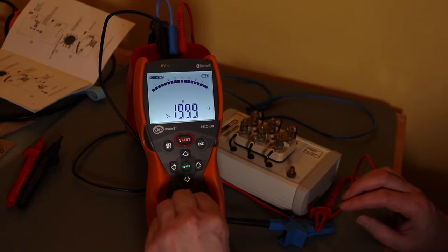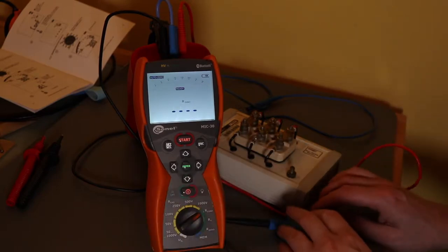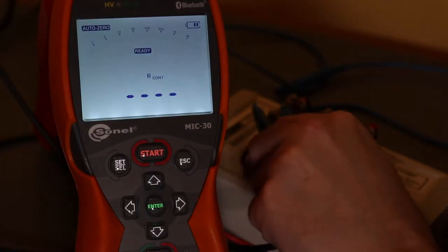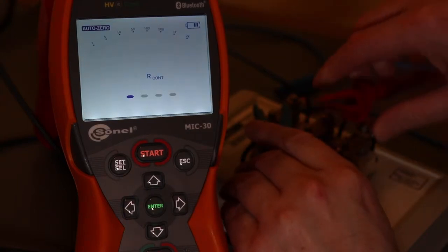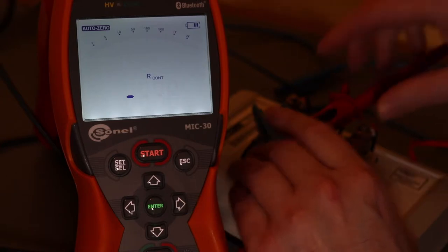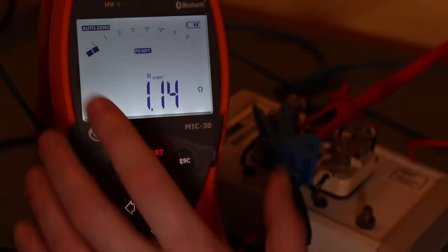Now I can move back to the continuity function and we'll go for the first winding resistance measurement. That's 1.14 ohms.